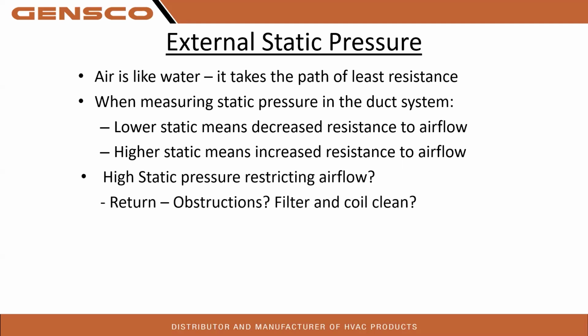Return obstructions. Well, if it's new construction, did the sheetrocker cover your return air? Do we have an undersized return? Did we put in a filter grill and now that filter is extremely dirty because it's 20 feet up in the ceiling and we can't get to it? Filter, again, I can't stress this enough: the number one reason for many different types of failures is your plugged filter.